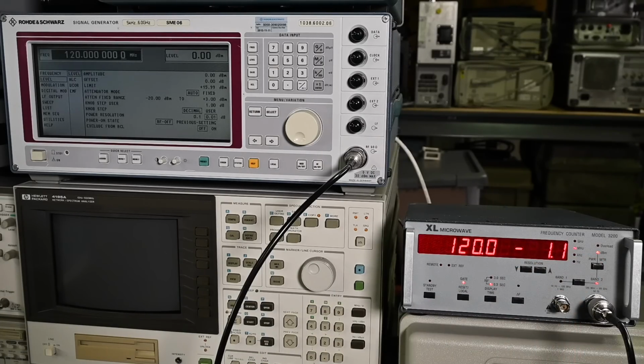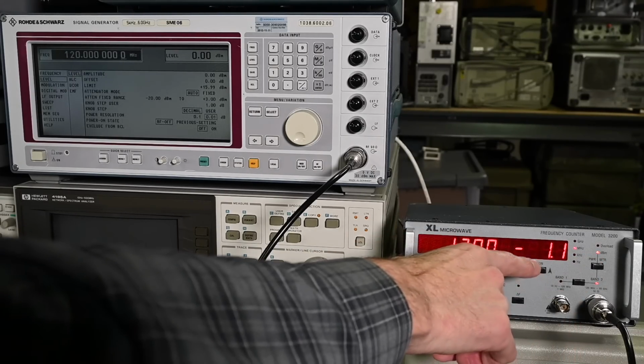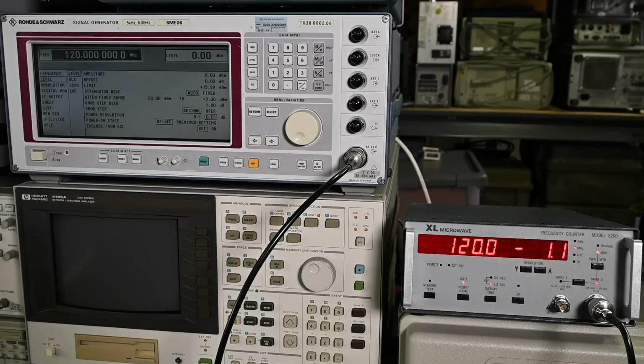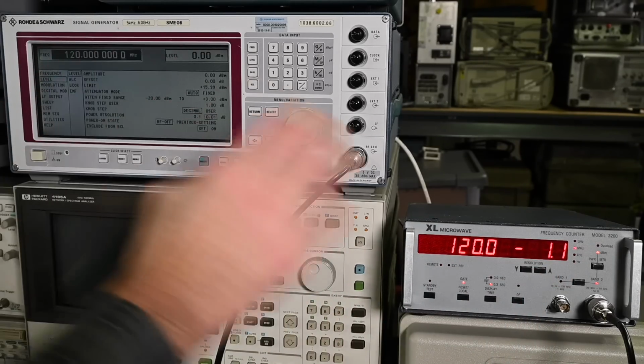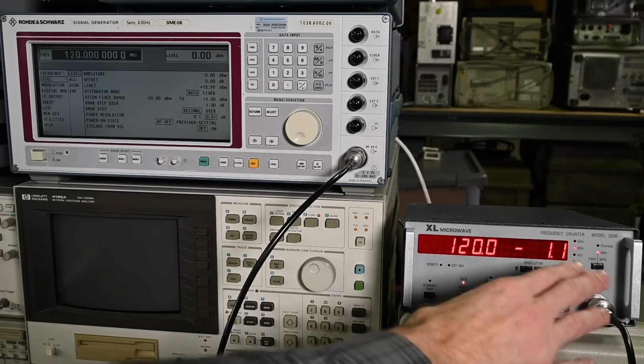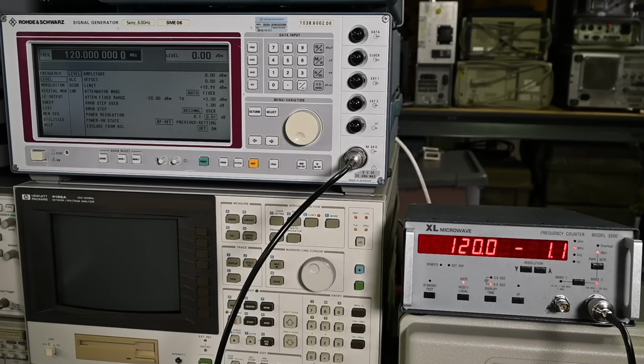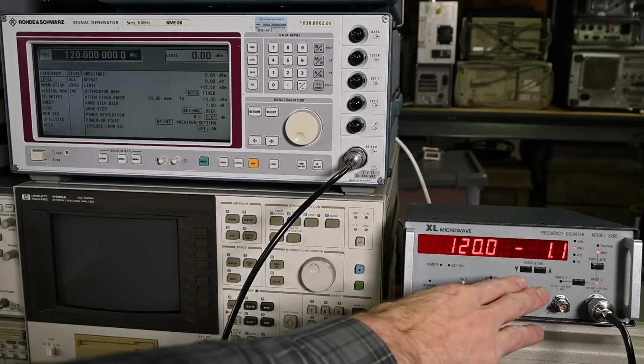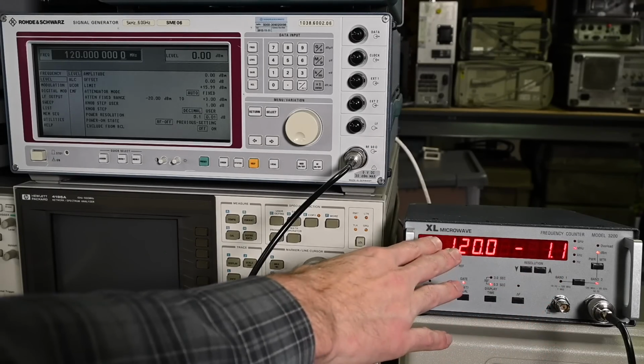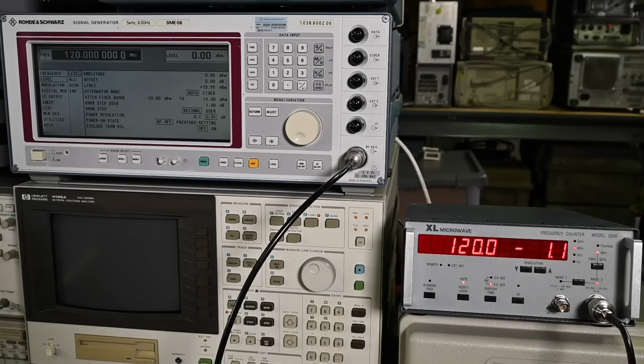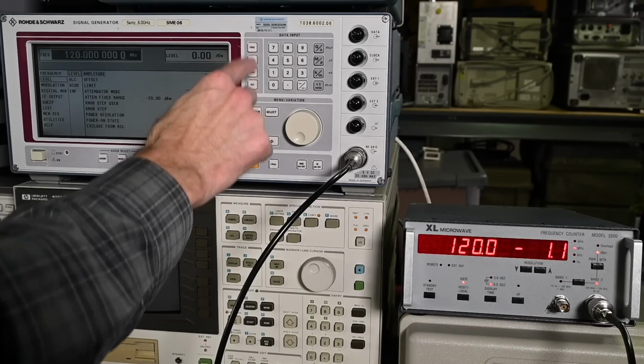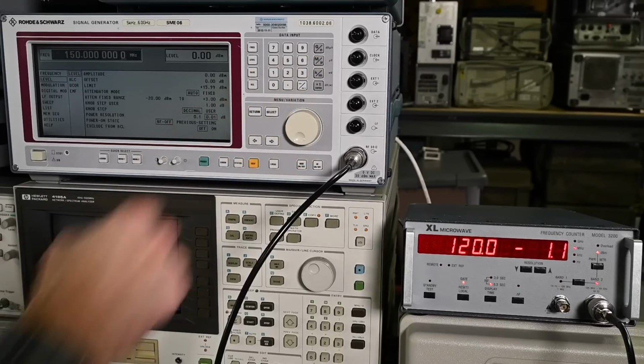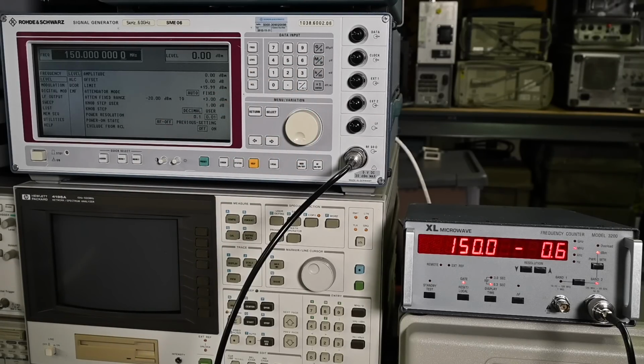So let's switch over to the power meter, because that's where the problem was before. So 120 megahertz and minus 1.1 dBm. So makes sense, being the frequency that's at the bottom end of this input, that's probably where it starts to drop off just a little bit anyways in its response. So not a concern. And earlier in the video, as you recall, 120 megahertz was way off on that value. So it looks perfectly fine, no problems there. Let's go up just a little bit. Let's say frequency 150 megahertz. We were using that value before. No problems with that, looks perfectly fine.